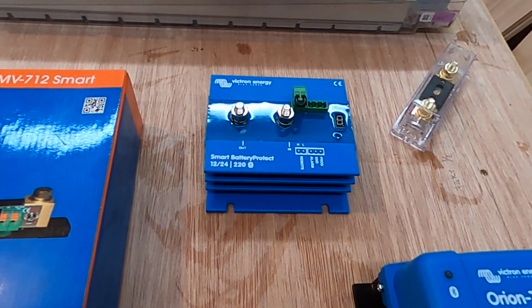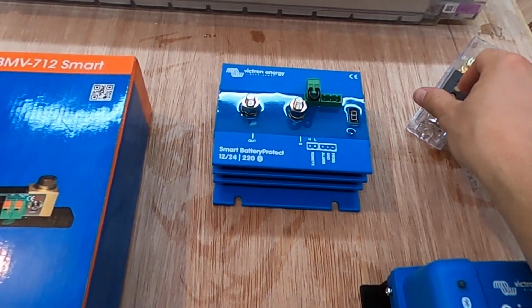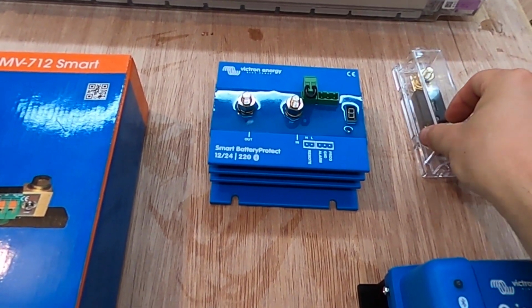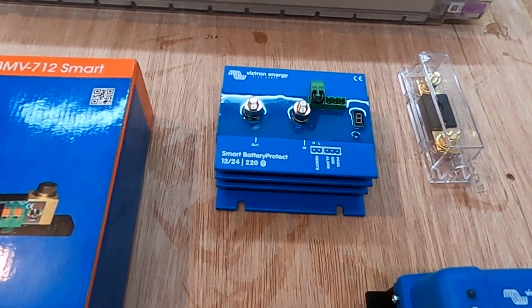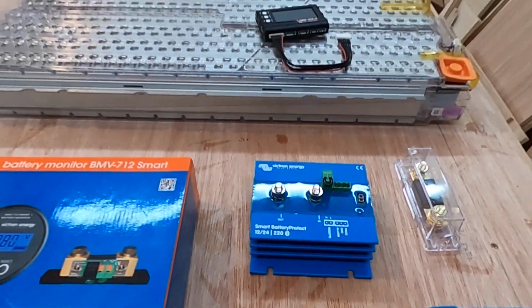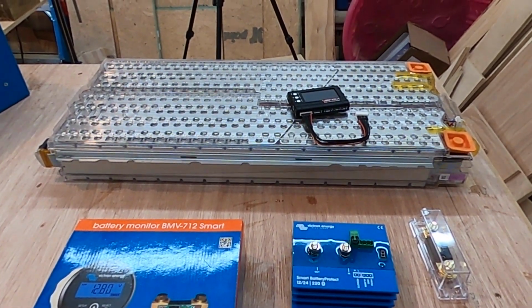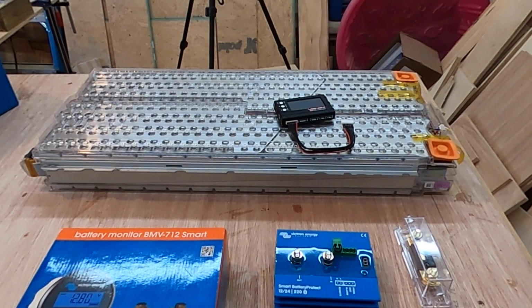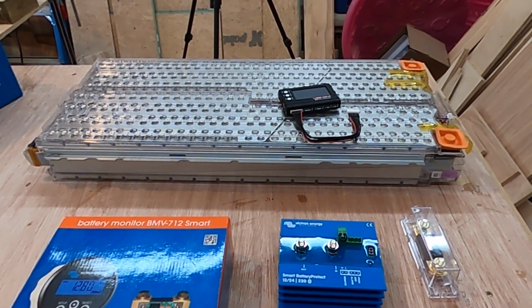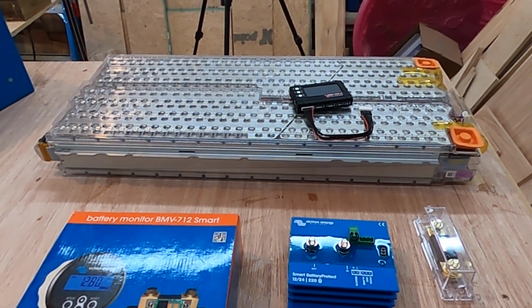On the other side of the battery protect is a 500 amp inline fuse. That is the final piece of protection - basically if anything overloads this battery and pulls more than 500 amps, we've got a serious problem, and we want that fuse to blow and protect our battery.